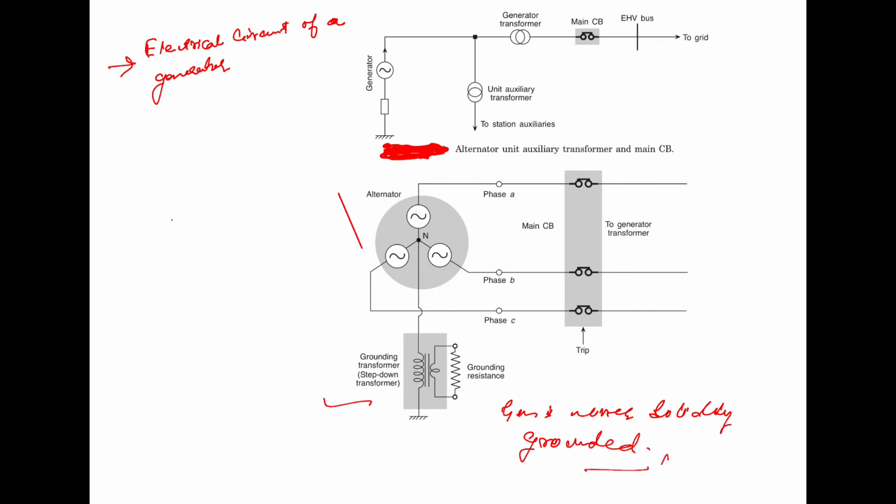Solidly grounded means that the resistance is equal to 0. If it were so, the single line to ground fault current would be dangerously high.